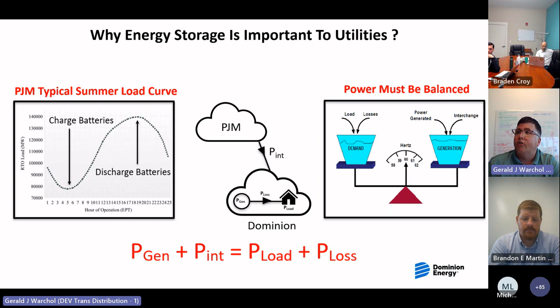Okay, so finally, we've got a little bit of background on why energy storage is important to utilities. We're now going to talk about our pilot projects. You'll see applications for all of these: primary application, secondary application. So this is the first one, in New Kent County. It is online as of Q1 2022. It's a Tesla Megapack system, 2 megawatts, 4 megawatt hours. So if I take that 4 and divide it by 2, I can inject 2 megawatts for 2 hours.